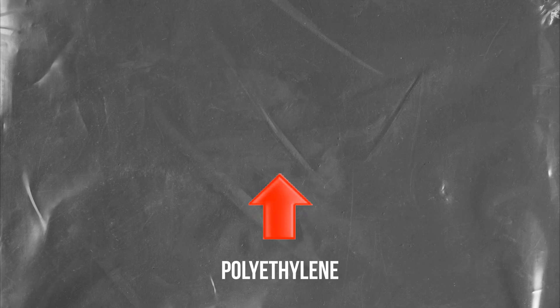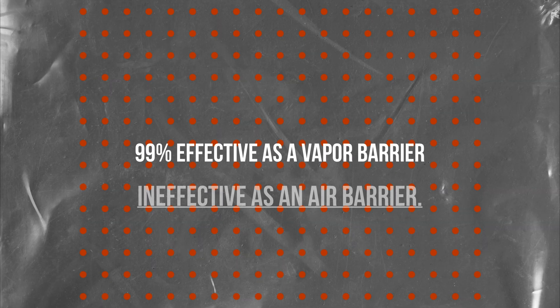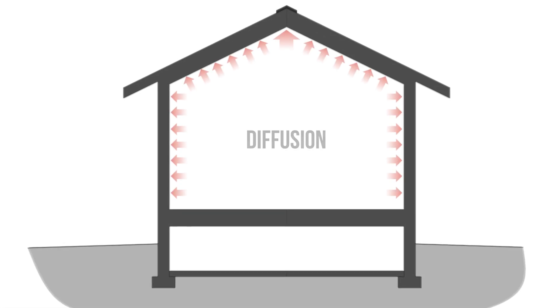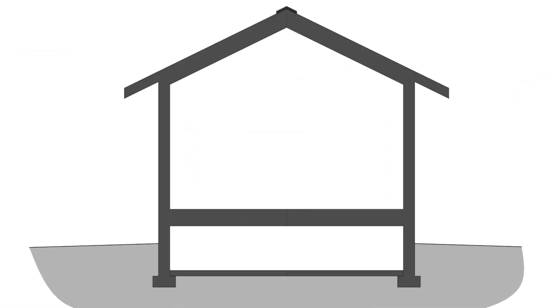Let's say we have a standard polyethylene vapor barrier, and we poke holes through 1% of the surface of that vapor barrier. That vapor barrier is going to be 99% effective, but as an air barrier, it's mostly ineffective. This is because vapor, when it moves through diffusion, acts upon the building evenly as a distributed load, whereas air leaks deposit that moisture in a concentrated load.